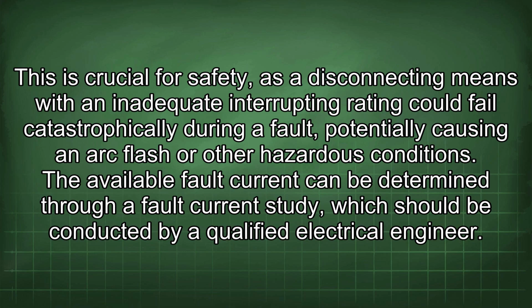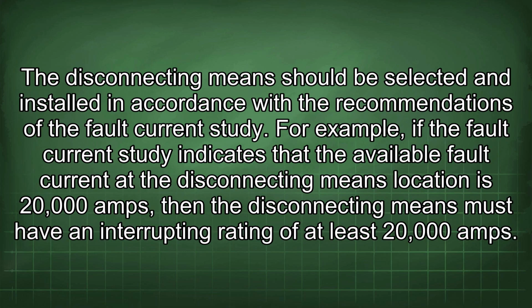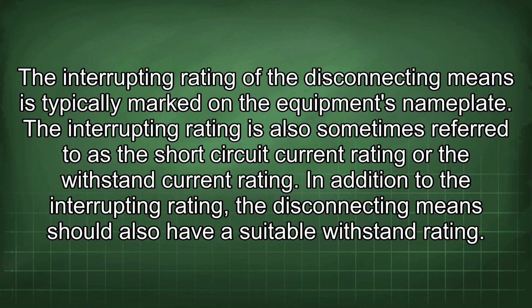The available fault current can be determined through a fault current study, which should be conducted by a qualified electrical engineer. The disconnecting means should be selected and installed in accordance with the recommendations of the fault current study. For example, if the fault current study indicates that the available fault current at the disconnecting means location is 20,000 amps, then the disconnecting means must have an interrupting rating of at least 20,000 amps.